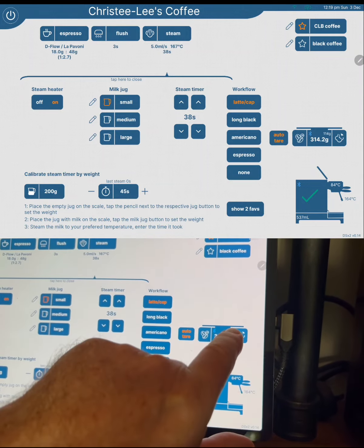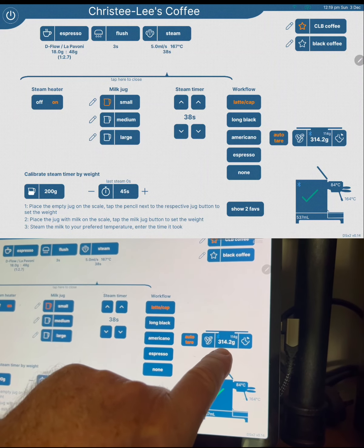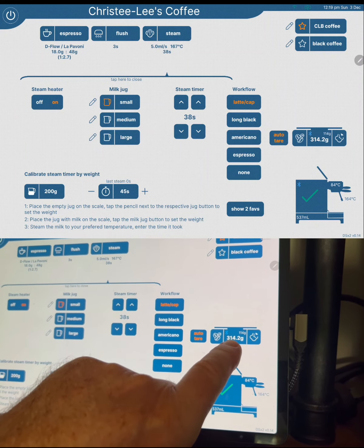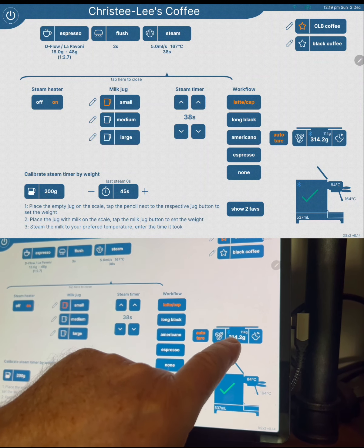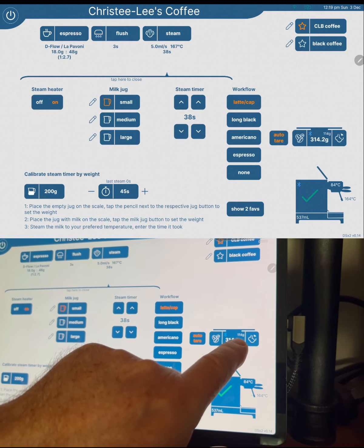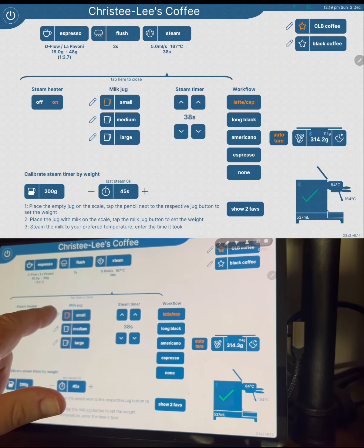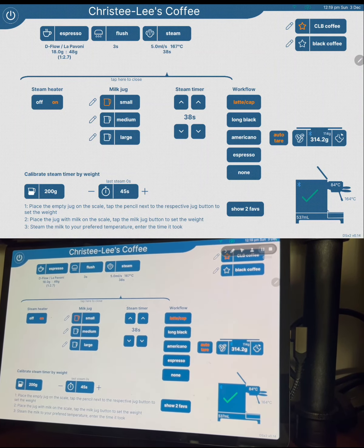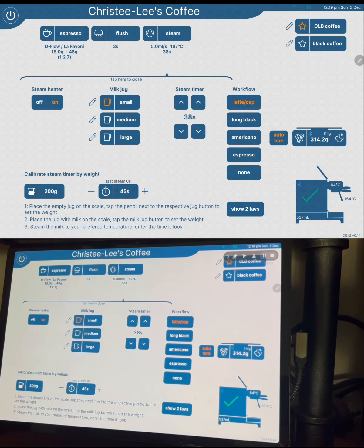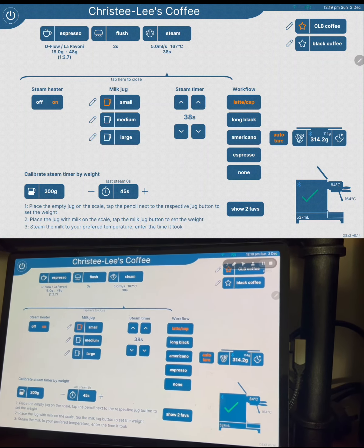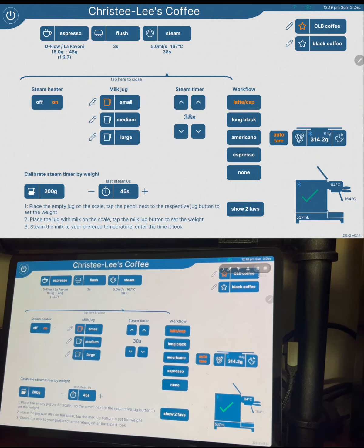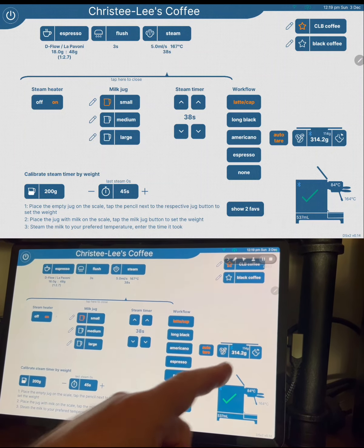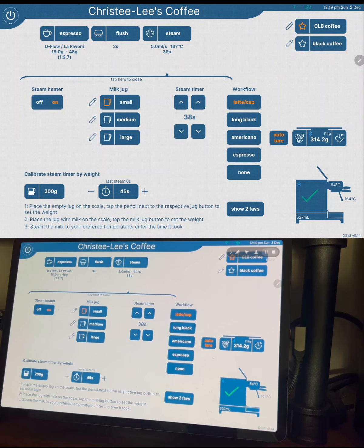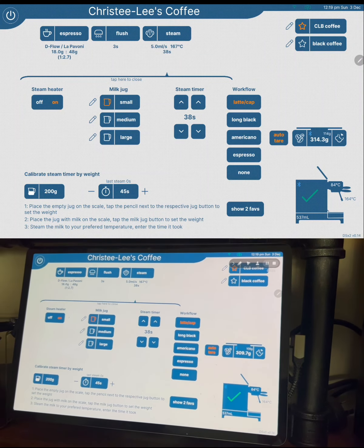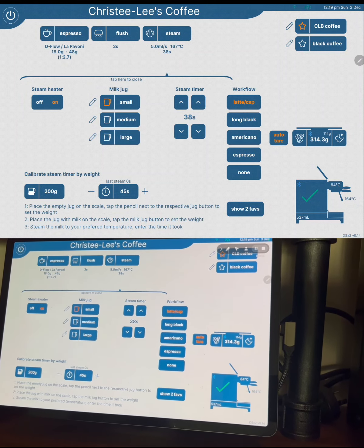Put the jug on there, and we can now see there's a small reading above the main weight reading. That main weight reading is the total weight of the scale with the jug with the water in it, and the small reading is that reading minus the value we've set for our jug, which works out to 114 grams. When we calibrate, it's best to calibrate close to the amount of milk you would normally use. I normally steam somewhere from 160 to 200 grams of milk, so I'm going to add more water and get it up to that weight.